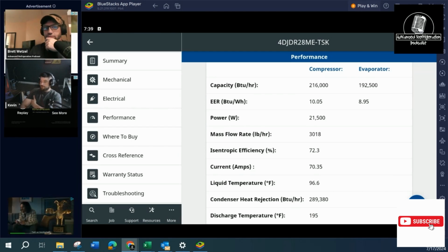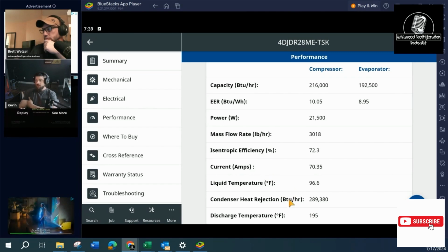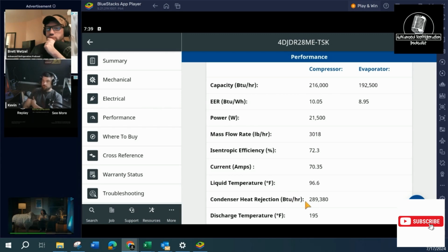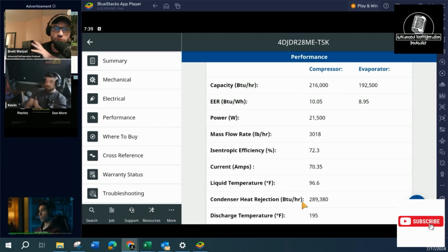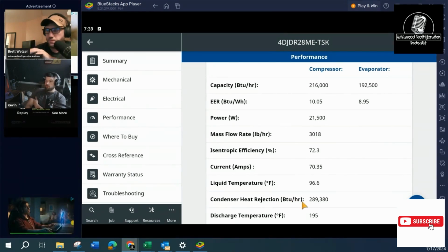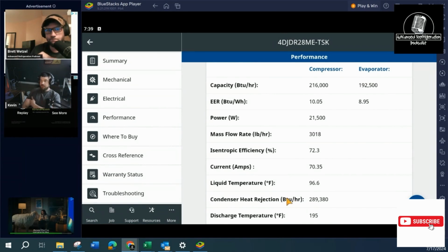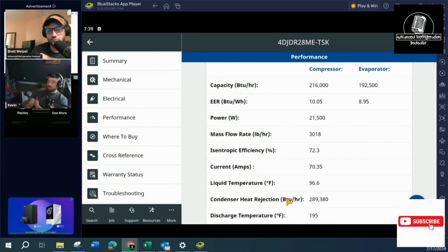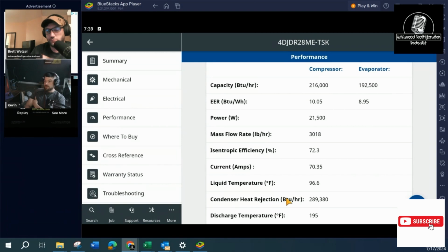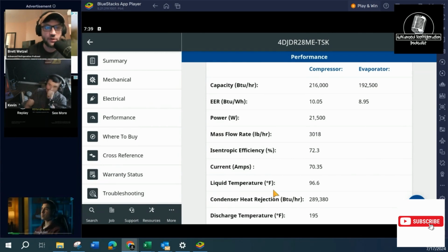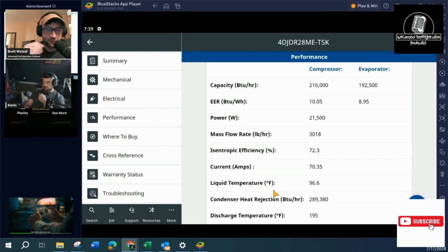It is. And then if you look down below, they gave you the condenser heat rejection, which here is 289,380. This would be the number that you would use to size a condenser. So that includes your heat of compression, and that includes your actual BTUs of your compressor. You can see it adds quite a bit of BTUs there, almost like 70,000. And then essentially that would be what you'd have to remove in latent heat, all right? Or I'm sorry, sensible heat.